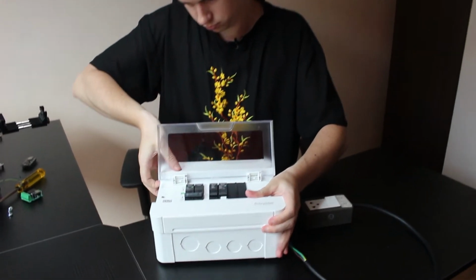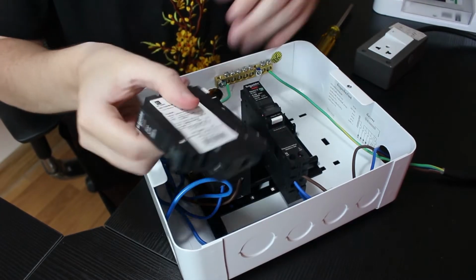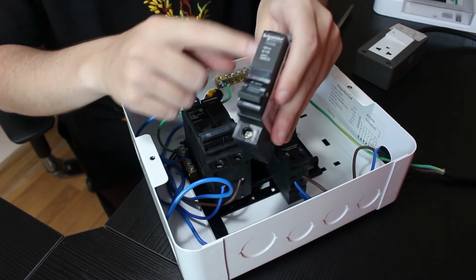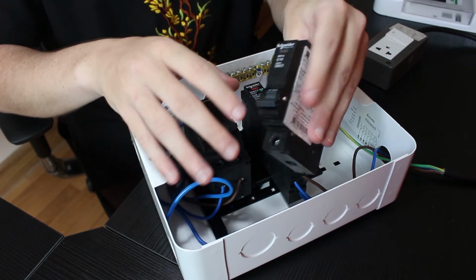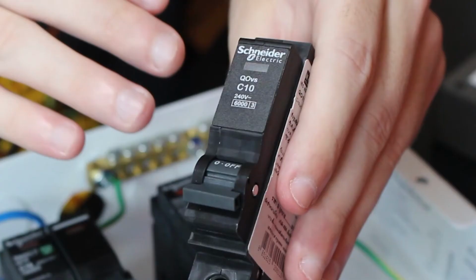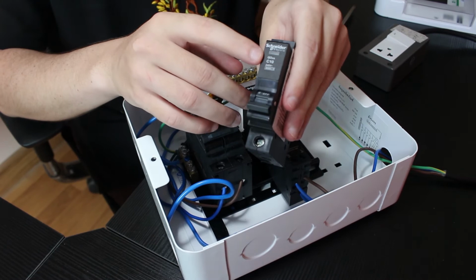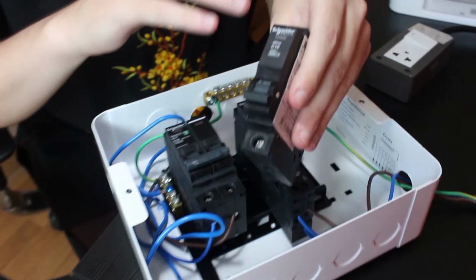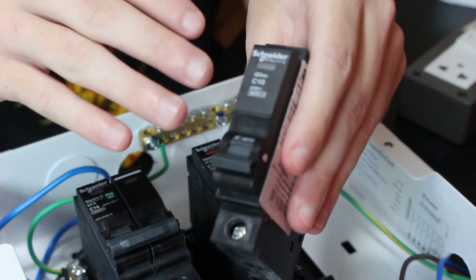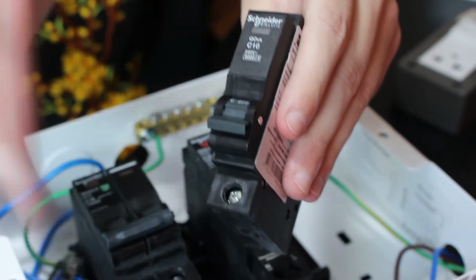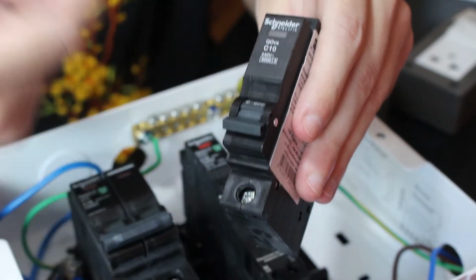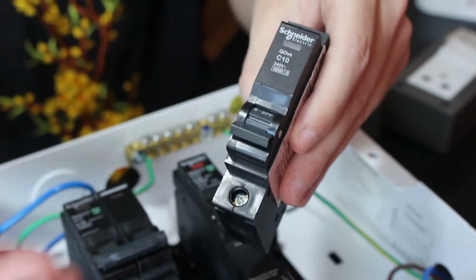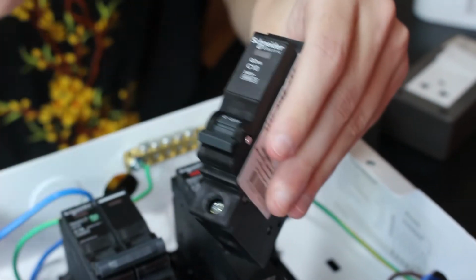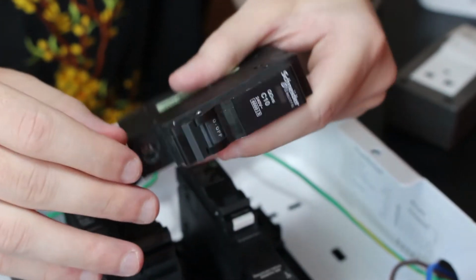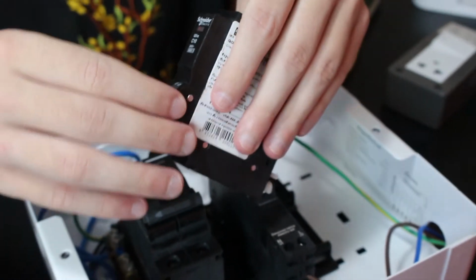First, we have these small circuit breakers that are very much standard. This one is a C10, meaning it cuts at 10 amps. It's extremely dumb — if there's more than 10 amps, it cuts, that's it. That's great to prevent fires: if there's a short circuit in your electronics, it's going to cut the power, hopefully before anything becomes bad.